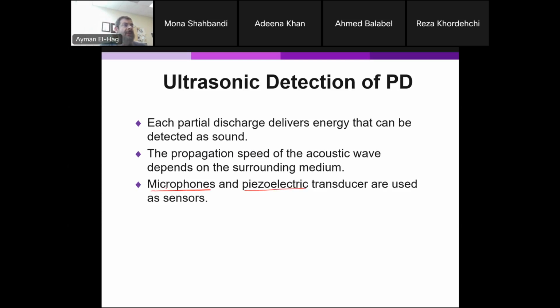Now, we use microphones whenever the partial discharge is what we call airborne. Airborne means the discharge happened in air, for example, if you want to detect partial discharge coming from the hardware in a substation. That's happening in air, and between the sensor and the source of the defect there is only air. So we use microphones, and microphones work either in the acoustic or audible range, or the ultrasonic.